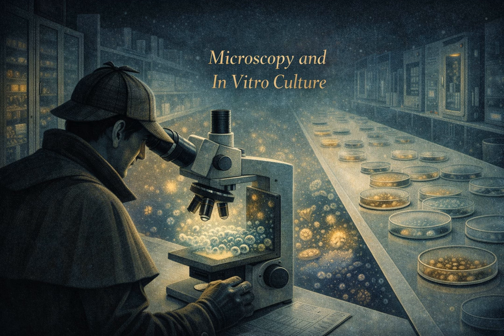Precisely. So by bridging that tiny air gap between the slide and the lens with oil, you effectively eliminate the air interface. The light now travels through the slide, through the oil, and into the lens as if it were one continuous, unbroken column of glass. It stops the scattering and captures those peripheral light rays that would otherwise have been lost to refraction. This dramatically increases the numerical aperture of the lens, which, in turn, improves the resolution.